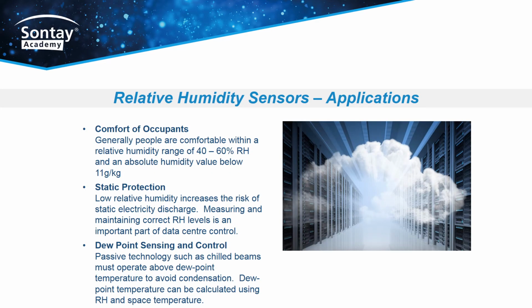Relative humidity sensors. Applications. The comfort of occupants. Generally, people are comfortable within a relative humidity range of 40 to 60% RH and an absolute humidity value below 11 grams per kilogram. Static protection. Low relative humidity increases the risk of static electricity discharge. Measuring and maintaining correct RH levels is an important part of data center control.